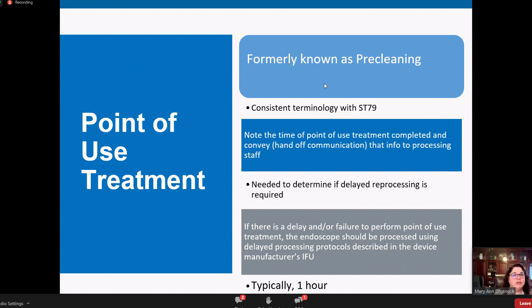So noting that time and conveying it will help stage scopes appropriately, knowing which ones have to get done when, because we don't want to do this delayed reprocessing, because long-term submersions on a frequent basis can lead to damage of the endoscope. So let's avoid that as much as possible by actually having an objective measure of that time between point of use treatment and manual cleaning in the scope room. So then we're going to go to transport of soiled endoscopes. So this is captured as a must within ST91.